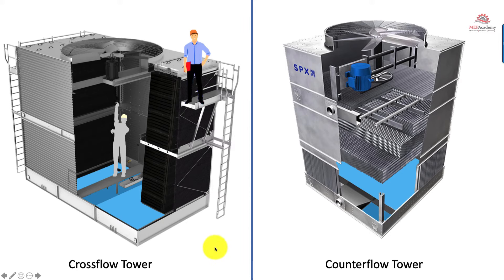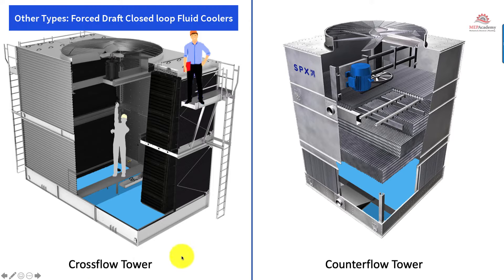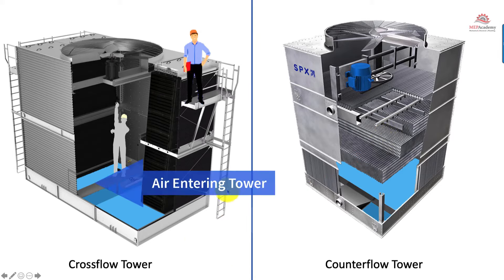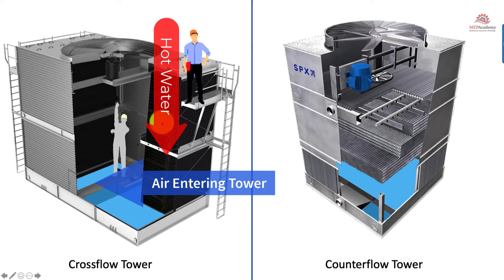There are two tower types: the cross flow and the counter flow tower. The difference is how the air enters the fill material. In the cross flow, the air entering the fill is horizontal while the water is trickling down vertically — air is horizontal — and that makes a cross, hence cross flow.